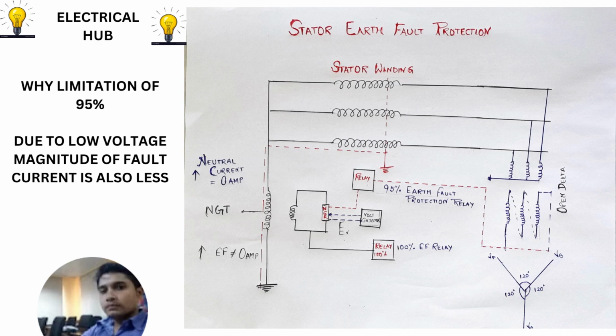Why the limitation of 95%? First, let us clear which part of the winding will be protected by the relay and which part will not. At the neutral end, 5% of the winding will not be protected by the stator earth fault relay, and that is why it is known as the 95% earth fault protection relay. The remaining 95% of the winding will be protected.